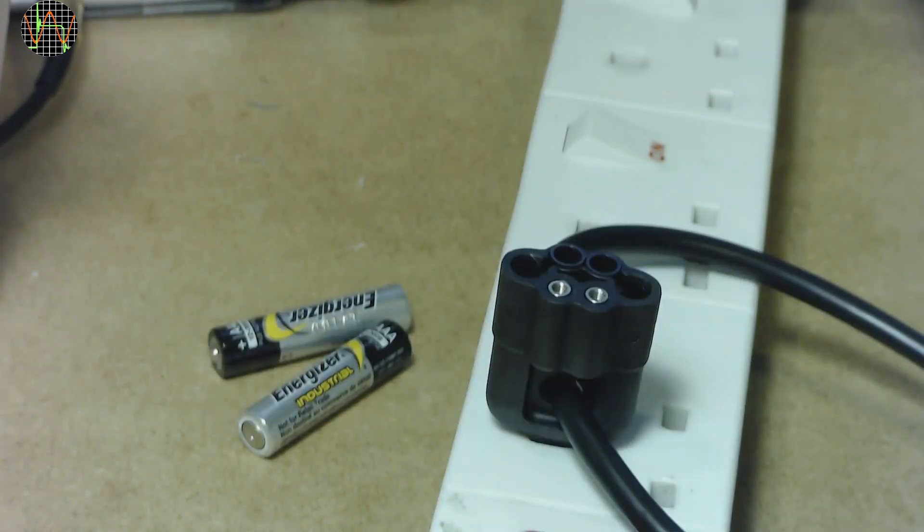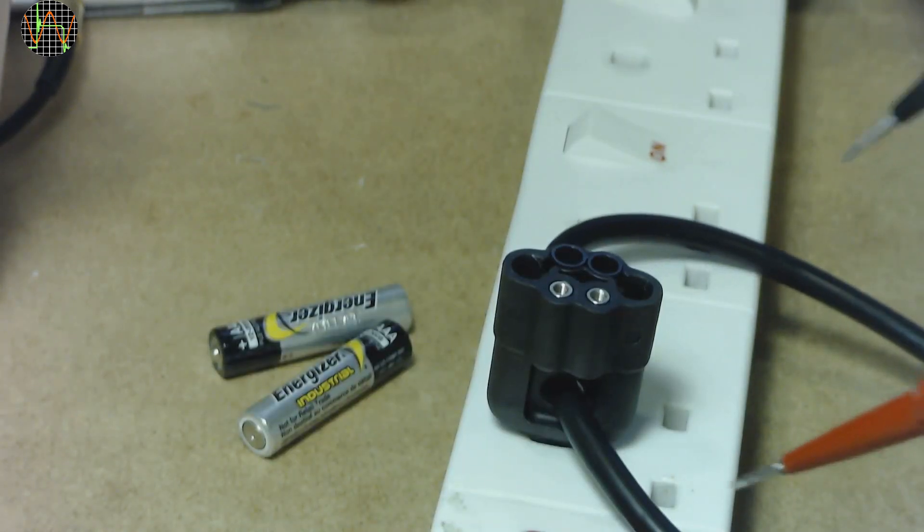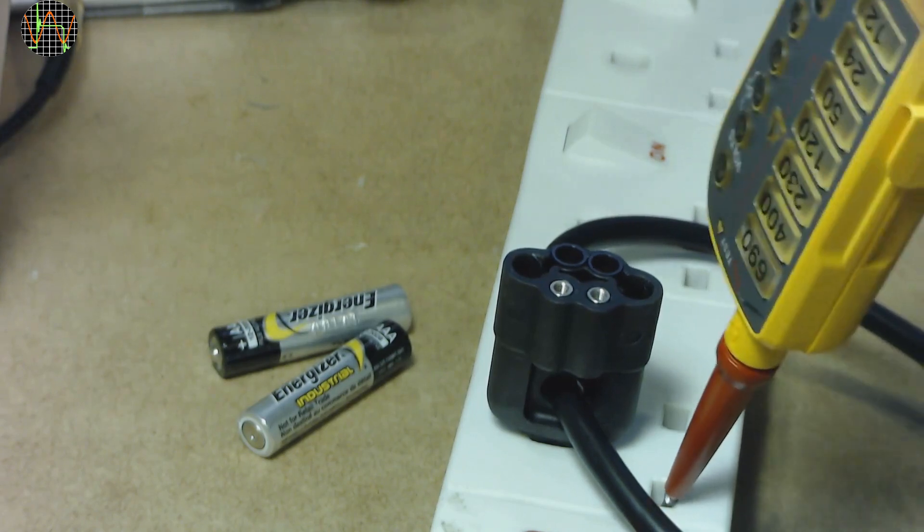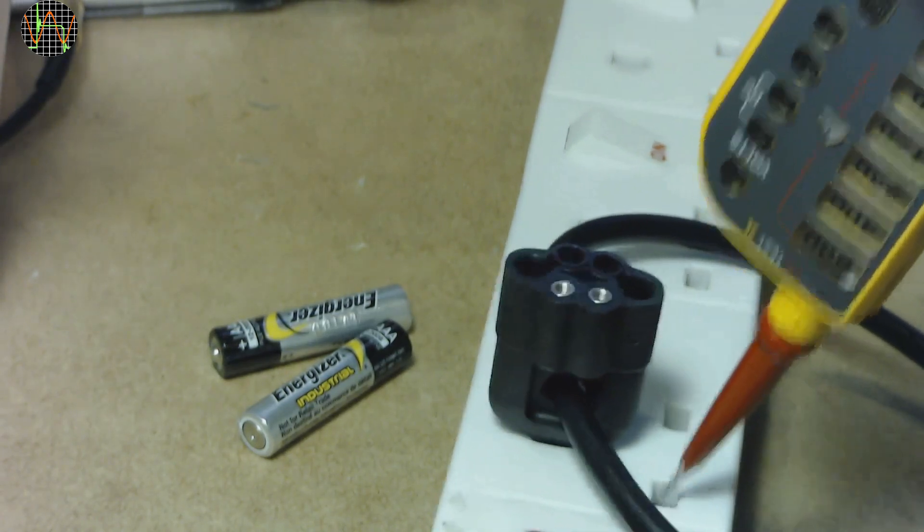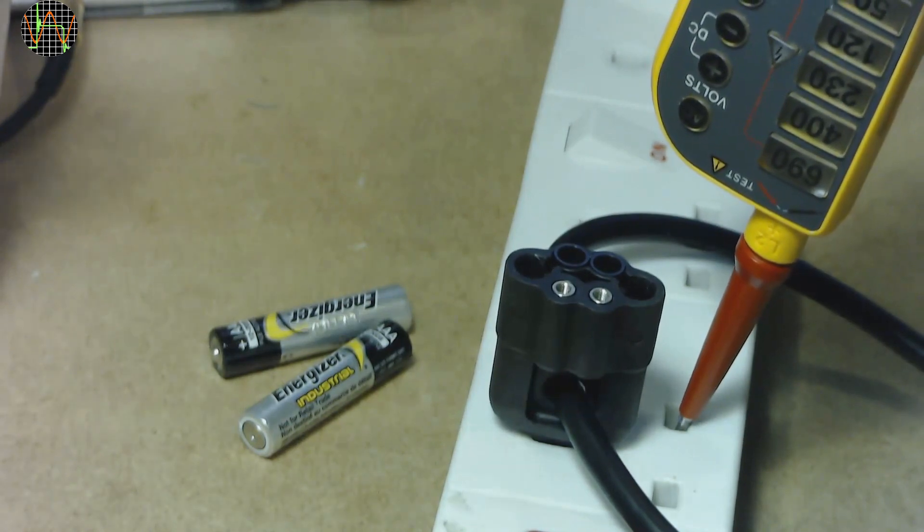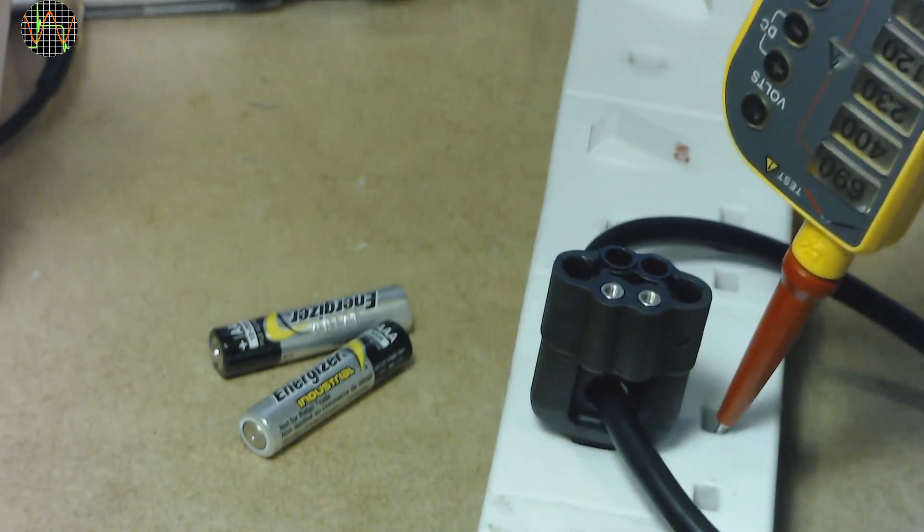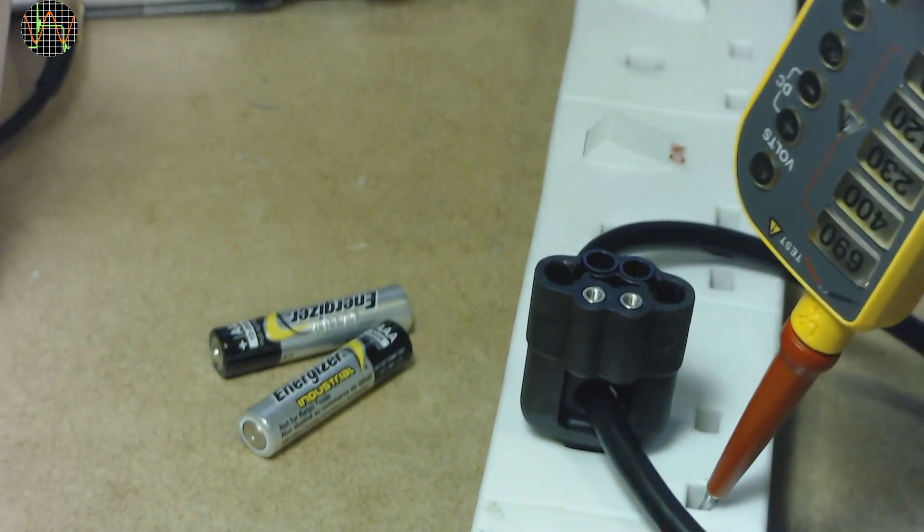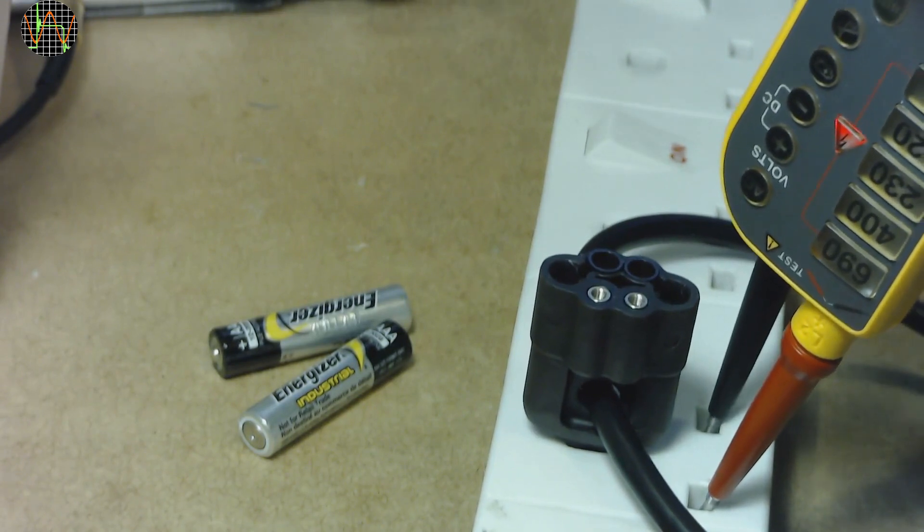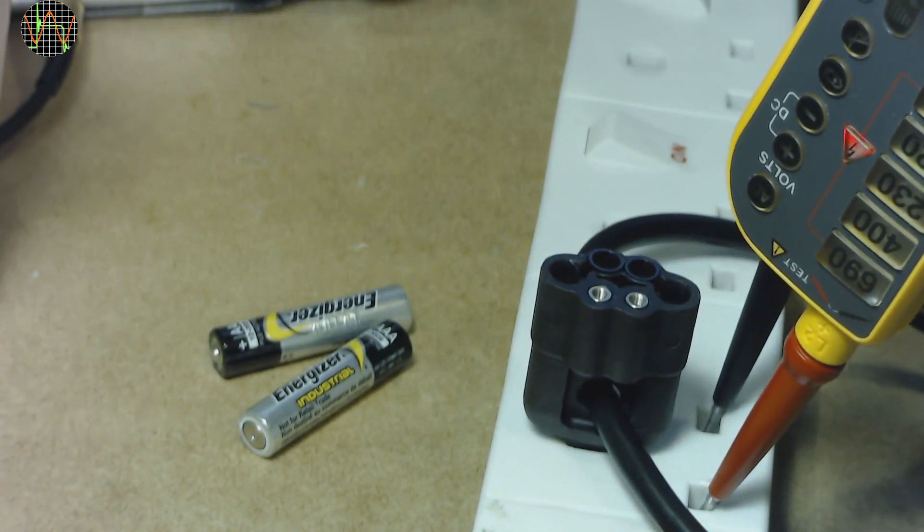Be aware that all of this only works if the batteries are okay. Let me show you what happens if they are dead or removed as in this case. Single pole phase test doesn't work anymore. In two pole mode, the triangular high voltage warning is the only indicator that still works to show that you are probing a live circuit.